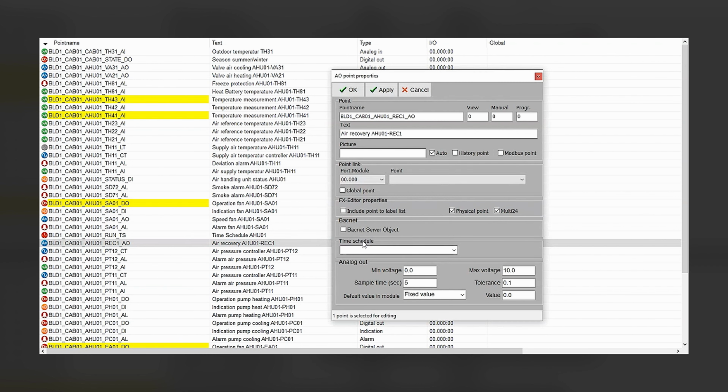The safety mode can be used by parameterizing the default value in case of a rupture in the communication with the serial Modbus Master FX controller of more than 30 seconds. Each channel can be configured to preserve its last output value or to change to a programmable value. Using another Modbus client than our FX controller, all parameters we just discussed can be set in the module's Modbus registers. You can find the detailed Modbus register description in the download section of the Fidelix Support Central.